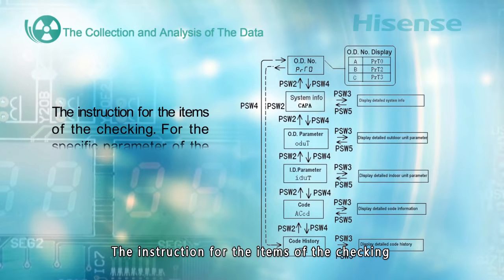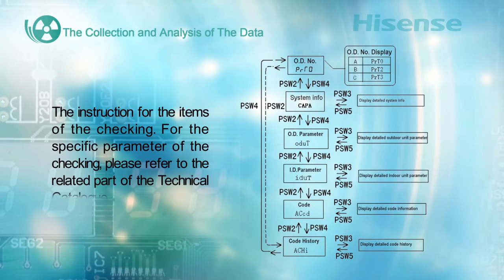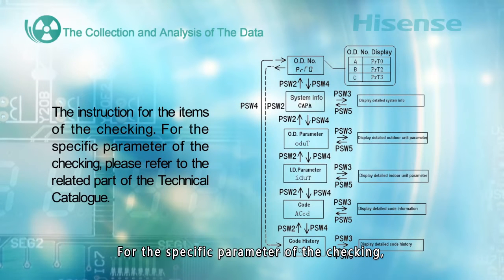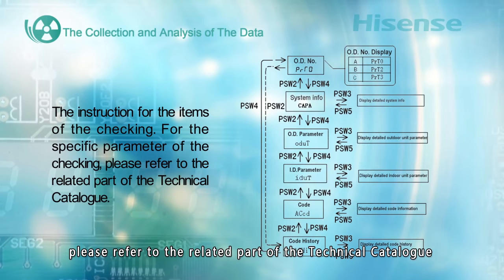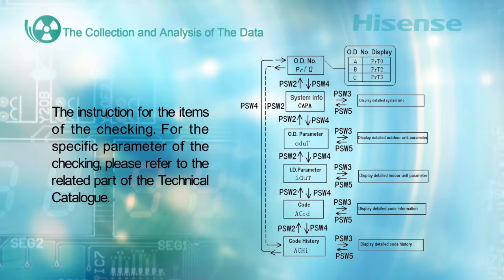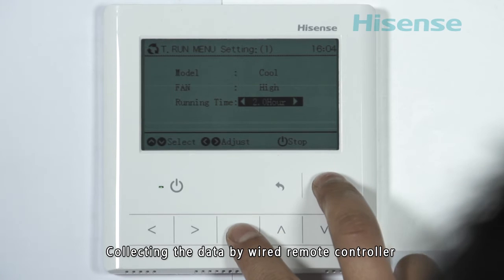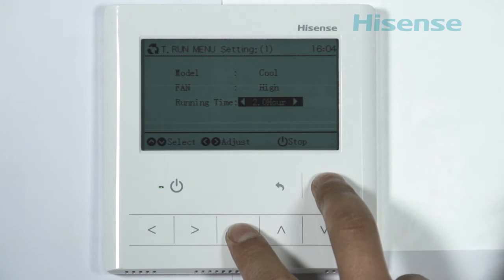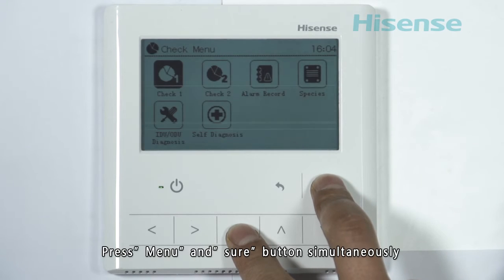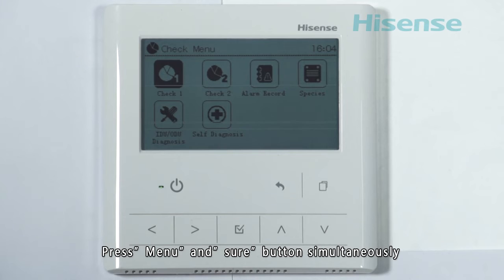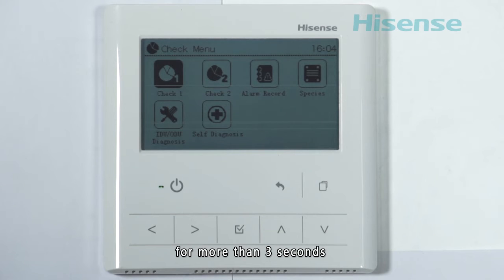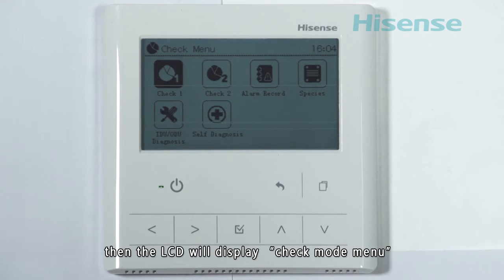The instruction for the items of the checking. For the specific parameters of the checking, please refer to the related part of the technical catalog. Collecting the data by wired remote control: under Test Run mode, press the Menu and Sure buttons simultaneously for more than 3 seconds. Then the LCD will display the Check Mode menu.